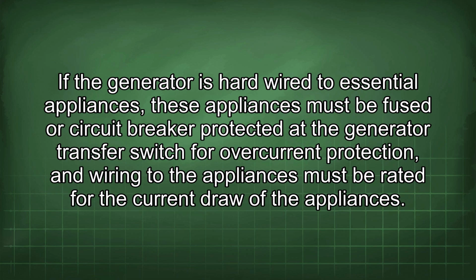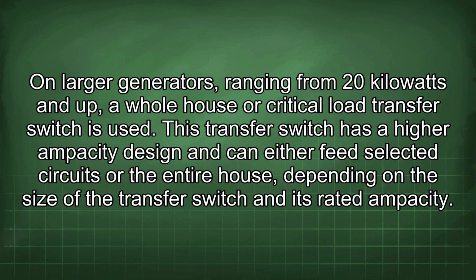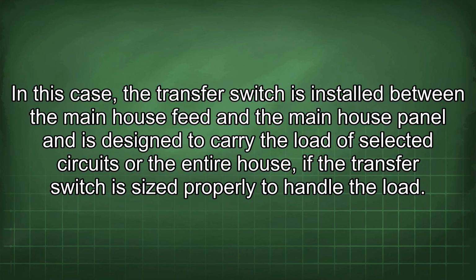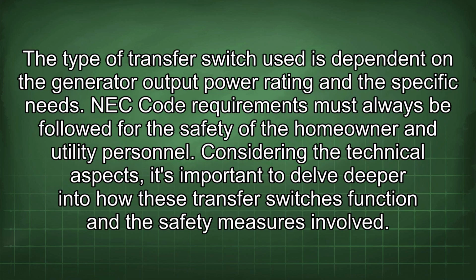On larger generators ranging from 20 kilowatts and up, a whole house or critical load transfer switch is used. This transfer switch has a higher ampacity design and can either feed selected circuits or the entire house, depending on the size of the transfer switch and its rated ampacity. In this case, the transfer switch is installed between the main house feed and the main house panel and is designed to carry the load of selected circuits or the entire house, if the transfer switch is sized properly to handle the load. The type of transfer switch used is dependent on the generator output power rating and the specific needs. NEC Code requirements must always be followed for the safety of the homeowner and utility personnel.